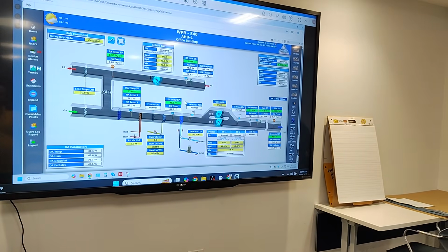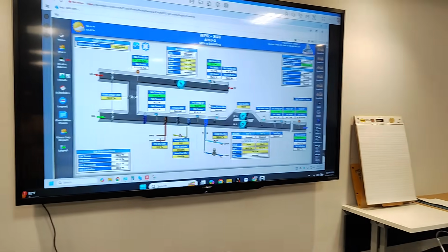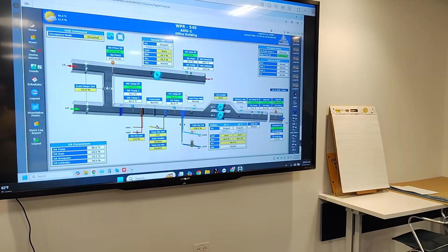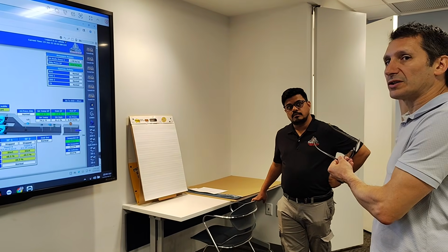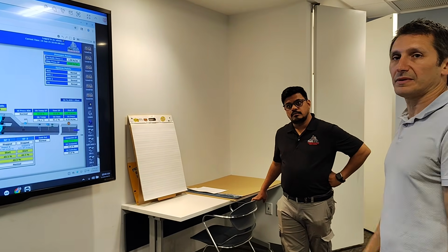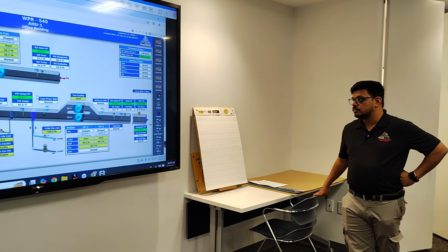It'll be like 33 hertz. We know when this thing was going down to minimum. We saw it at minimum. We saw when he ramps it, so we know that that's working. Can I run up to the 3rd floor and actually look at the temperature? Because right now we don't have eyes on this.